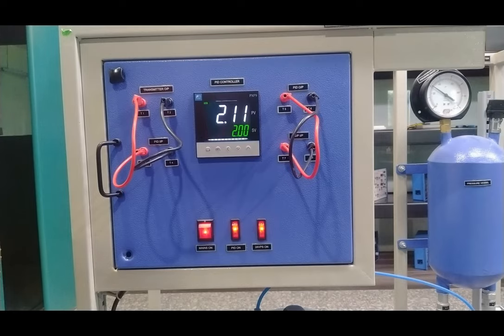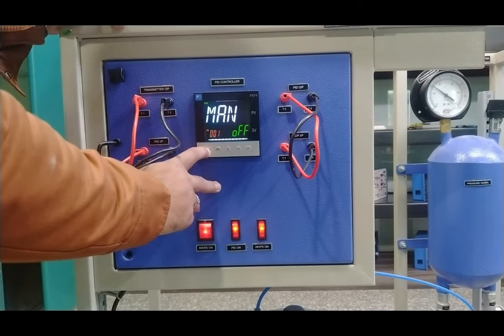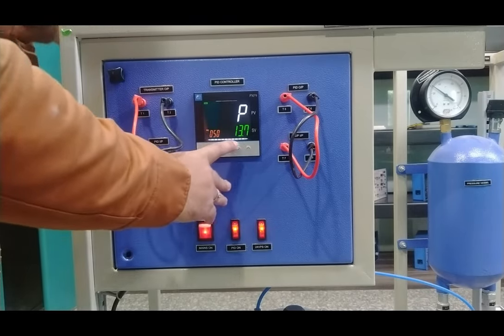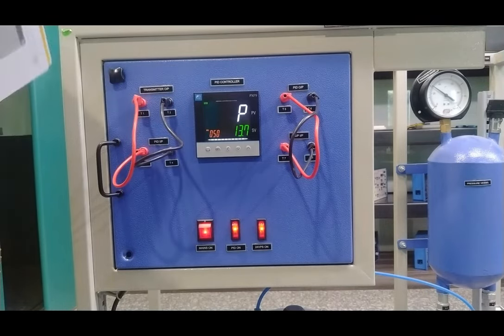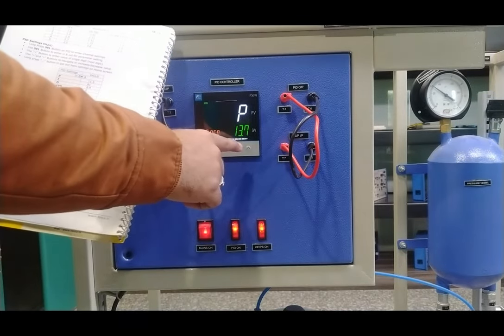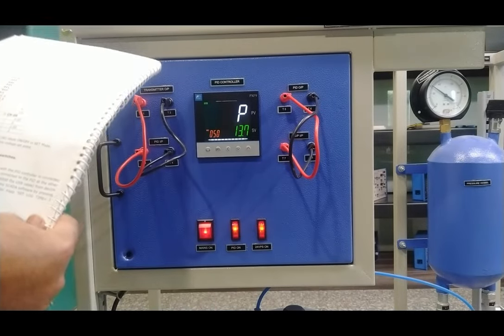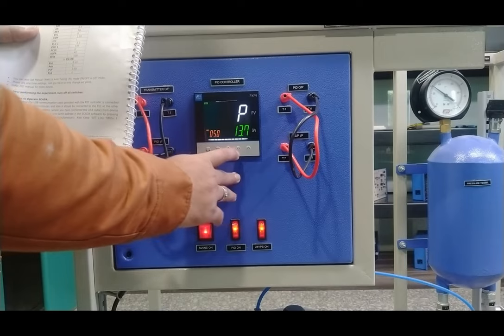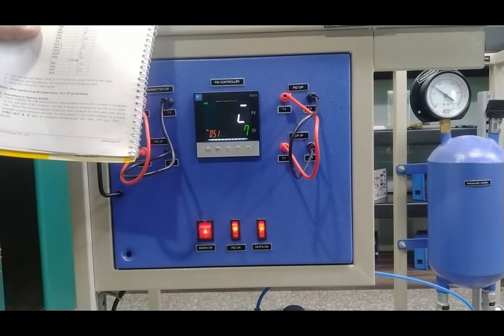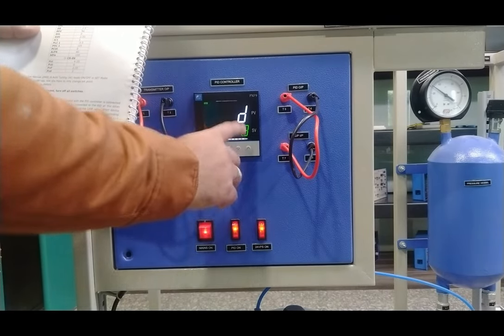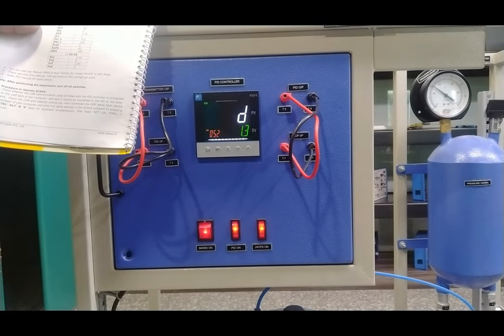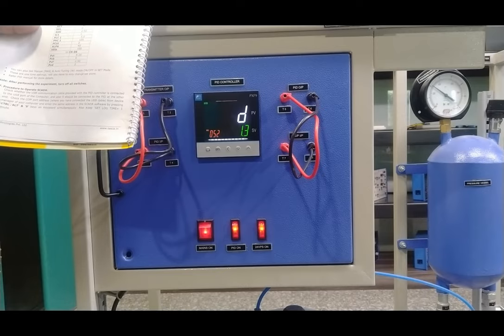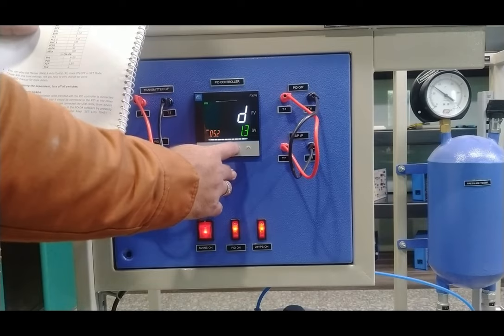You can observe the valve position continuously opening and closing as automatic tuning with the system and plant goes on through the PID controller. Auto-tuning has been completed and the set point is achieved. After auto-tuning, you can observe the PID values which have been changed — note down all the PID values and other values entered before, as these values will change according to your system and pressure line. Going back to the PID menu by pressing select for three to four seconds: before auto-tuning the P value was 11.5; after auto-tuning it is 13.7. The I value was 81 and is now 7. The D value was 8.9 and is now 1.3. These depend on your specific system — values may differ from person to person and process to process based on air supply and other components.